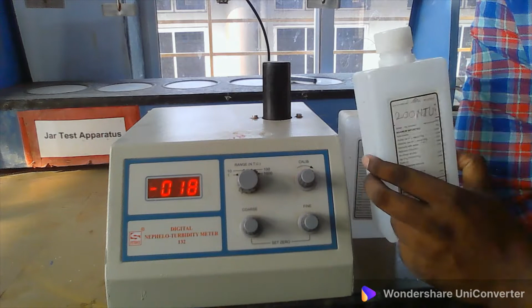Then the second knob is the calibration knob. First we put the standard solution and do the calibration. With the help of this we adjust the exact value of the solution of formazin. If it is 200 NTU, then we calibrate up to 200 NTU. If the reading is greater or less than 200 NTU, we move this knob in the forward and backward or circular direction and adjust it to set the reading exactly equal to the strength of the solution, that is formazin. This is the description of the second knob.